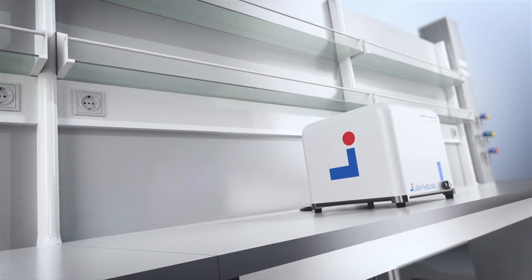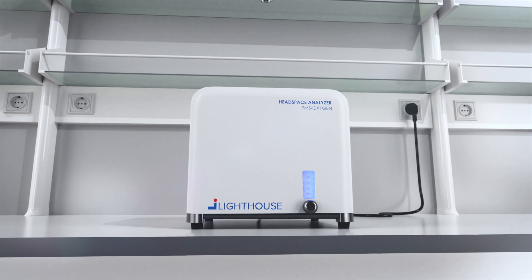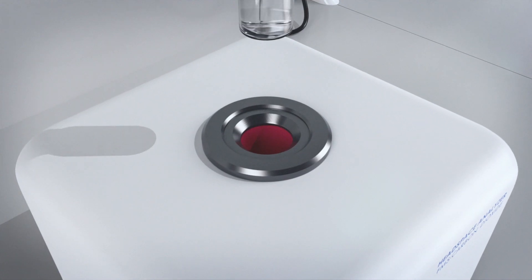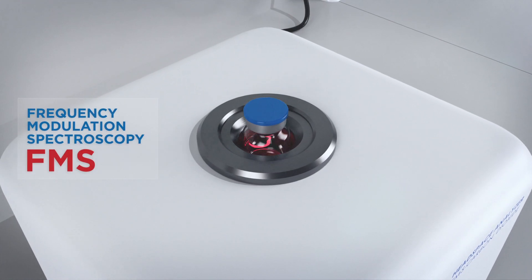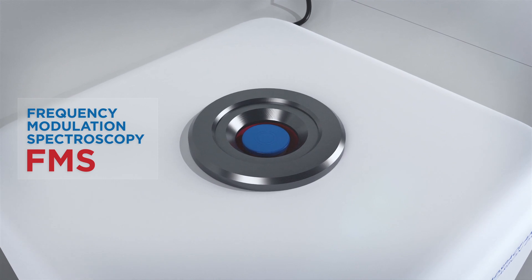The Lighthouse FMS Oxygen Analyzer measures headspace oxygen levels in sealed parenteral containers. This compact benchtop instrument utilizes a high sensitivity laser absorption technique known as frequency modulation spectroscopy.